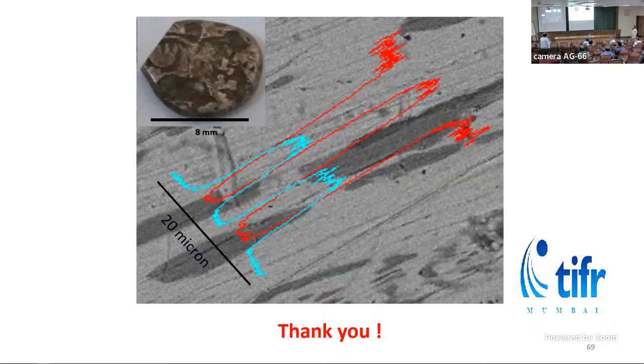So I understand these go all the way to a fraction of nanometers, tens or maybe hundreds. So is there a procedure where you do something like a calibration from time to time, that tells you that your instruments are looking at the least counts which are expected? Is there some procedure like that? Yes, we have standard samples and we have to calibrate the equipments from time to time. And for the aberration corrected microscope, we have to align the microscope using those standard specifications, and that alignment procedure itself takes quite a long time.